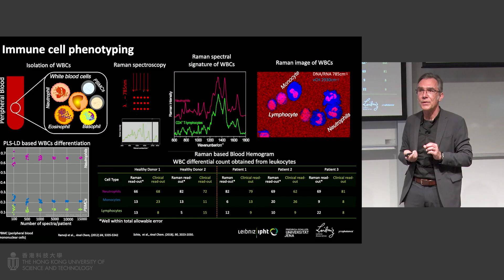Now, coming back to this device, this is very particular. We use light scanning, we use a rapid mean spectral acquisition, and mean spectral acquisition means we have just one spectrum taken per cell. So we open up the focal plane. This means we have a focus which is 8 micron in diameter, so we can take one spectrum, we get an average spectrum. And what is also quite important, we have completely automated everything.